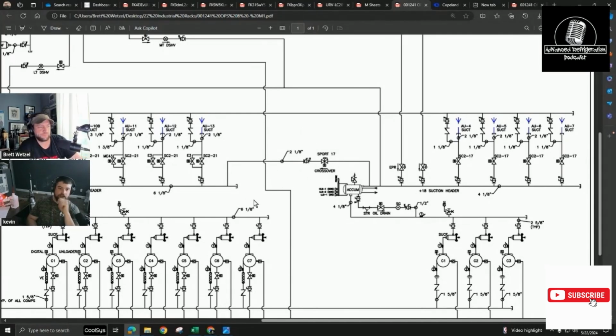You want to set it so it's going to pull from the lower header, not the higher header. So what you'll generally do is shut down some of the loads on the other side and set it to where it's like a pound or two above whatever it's supposed to be at, maybe 3 or 4 pounds. That way it keeps the other header loaded all the time from ever shutting off.